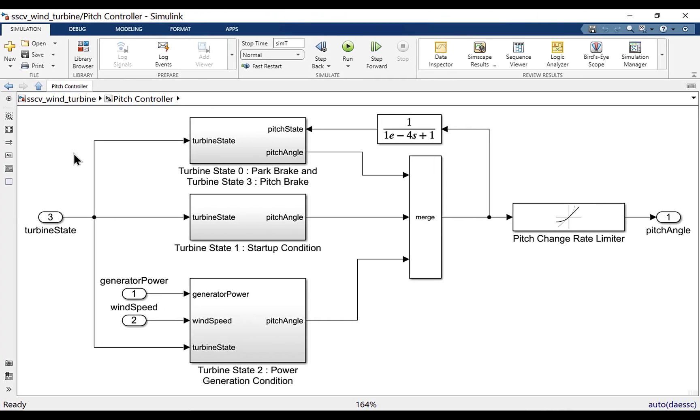The turbine pitch controller decides the angle of the rotor hub blades based on the turbine state received from the supervisory control. If the turbine is in pitch brake or park brake mode, the angle is pitched to the maximum possible pitch angle. If the turbine is in startup mode, the angle is pitched to the minimum possible pitch angle.